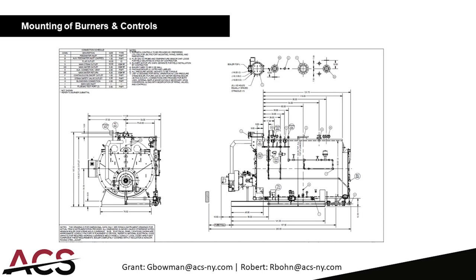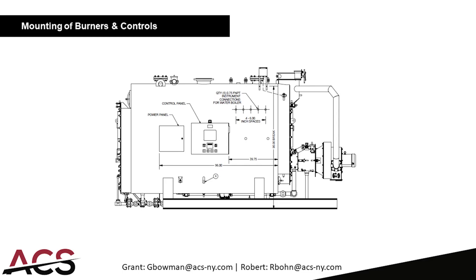You can also see the trim on the boiler — they have a probe-style water level and also a float, plus a continuous blowoff with controller. On the left side of the boiler there's a control panel and a power panel next to it, which takes in high voltage power and distributes 120V to the control panel and high voltage to the blower motor and air compressor if it's oil. It's good practice to bring the high voltage into a power panel rather than directly into the control panel, to avoid electrical noise.